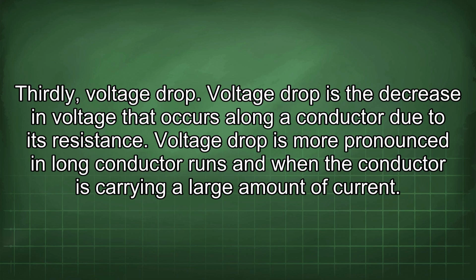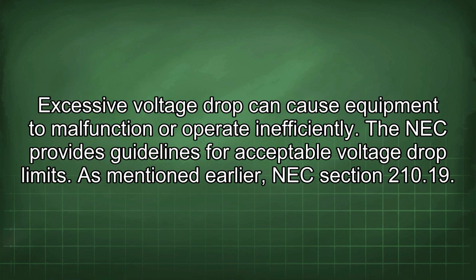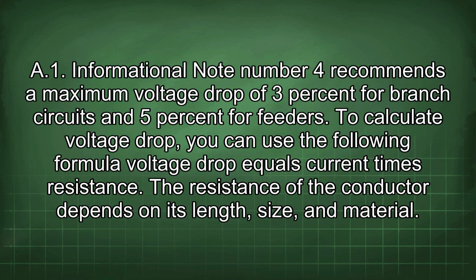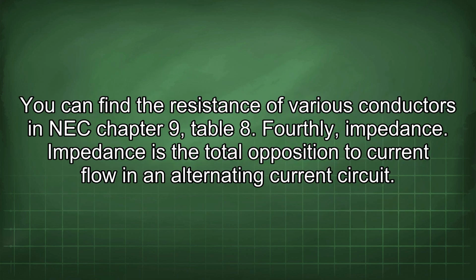Voltage drop is the decrease in voltage that occurs along a conductor due to its resistance. Voltage drop is more pronounced in long conductor runs and when the conductor is carrying a large amount of current. Excessive voltage drop can cause equipment to malfunction or operate inefficiently. The NEC provides guidelines for acceptable voltage drop limits. As mentioned earlier, NEC Section 210.19(A)(1), Informational Note Number 4, recommends a maximum voltage drop of 3% for branch circuits and 5% for feeders. To calculate voltage drop, you can use the following formula: voltage drop equals current times resistance. The resistance of the conductor depends on its length, size, and material. You can find the resistance of various conductors in NEC Chapter 9, Table 8.